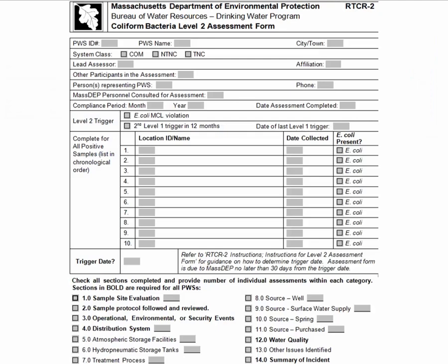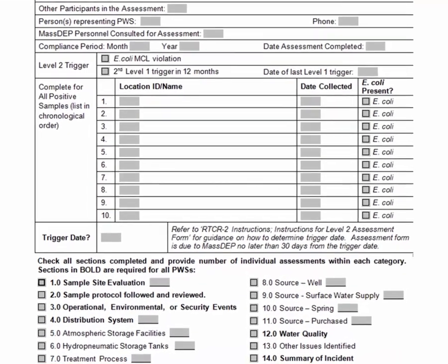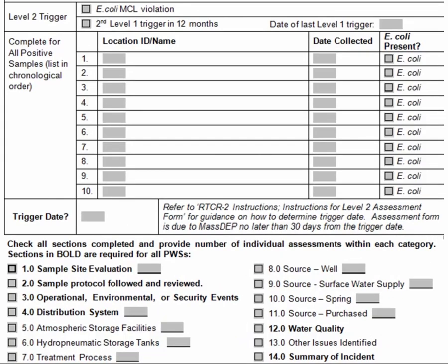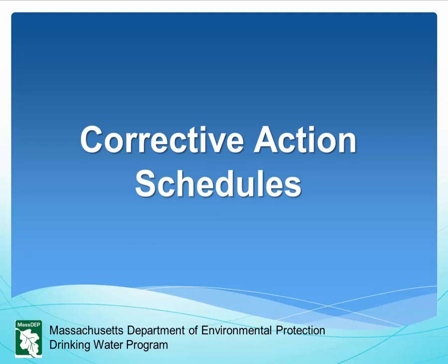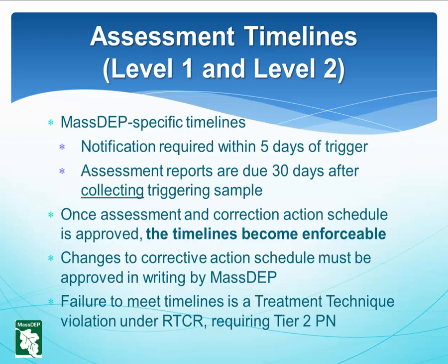Here is what the beginning of the Level 2 assessment form looks like. Just like the Level 1 form, basic system information is required, and there are multiple sections to complete. The bold sections at the bottom of the page are required of all PWSs. Regarding corrective action schedules and timelines: notification is required within five days of triggering an assessment, but a system should not wait until the last day since assessment reports are due 30 days from the triggering sample collection date. Once the assessment and proposed corrective action schedule is approved, the timelines become enforceable. Any changes must be approved in writing by MassDEP. Failure to meet timelines is a treatment technique violation under the RTCR, requiring Tier 2 public notification.